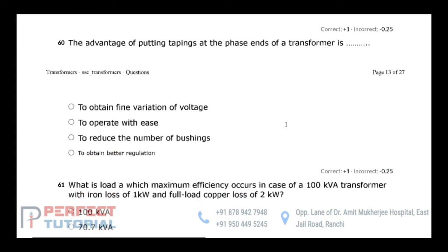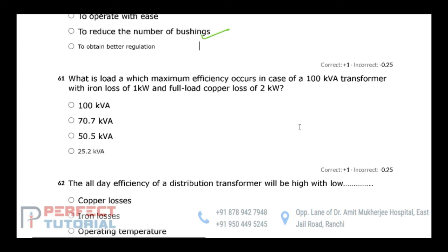Next, the advantage of putting tappings at the phase ends of a transformer is that it purposefully reduces the number of bushings on the transformer. Next, what is the load at maximum efficiency in the case of a 100 kVA transformer with iron loss of 1 kilowatt and full load copper loss of 2 kilowatt?